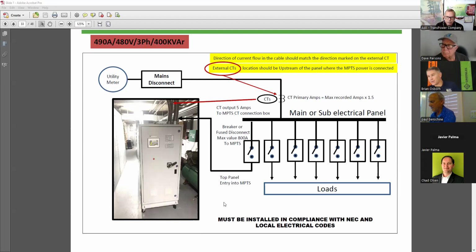And then a lot of this, you really did emphasize the CTs and making sure that you get your power metering installed correctly. I thought it was interesting that the CTs are customer supplied, but after thinking about that, it makes a lot of sense because every electrical installation is going to be unique as far as the needs for the CTs, how big the CTs are, and the length of the lead wires coming off the CTs has to be considered so that you're not splicing them.